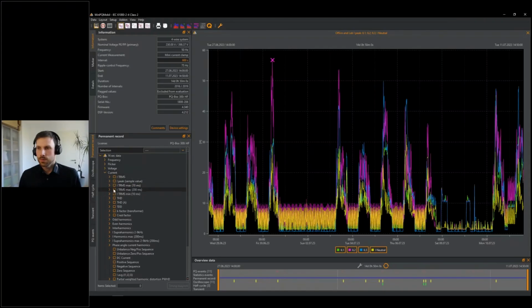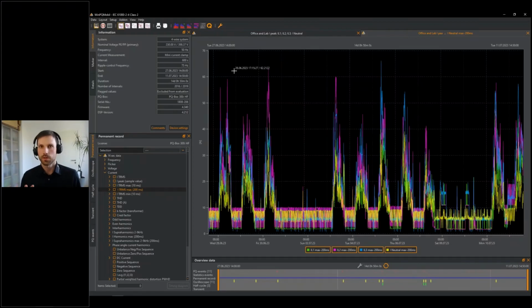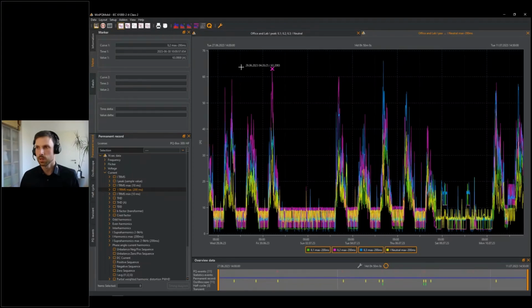I can also check the maximum values. We have different maximum values. We have the 200 millisecond value. If I open this, there are 5 of them per second, and it covers 10 cycles in the 50 Hertz network or 12 cycles in the 60 Hertz network. And this is way higher. Well, it's a bit higher than the 56 amps because we only look at a 200 millisecond time window instead of 10 minutes. Then there's a 10 millisecond value as well, so a half cycle value.